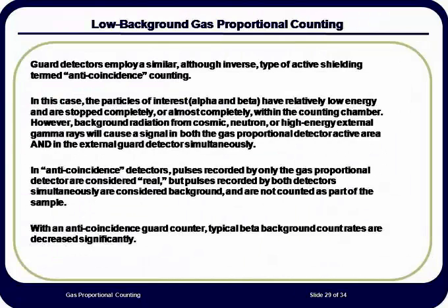In a gas proportional counter, a guard detector may be installed with the instrument. All alpha and beta particles from decay of environmental radionuclides will be shielded from the sample detector by the passive lead shielding. However, cosmic radiation will penetrate the active guard detector and may cause random events in both the guard and the sample detectors. When this occurs, the system is set up to discard those counts as not being from the sample. This is referred to as anti-coincidence, since when counts are recorded simultaneously in both detectors, the counts are not recorded.